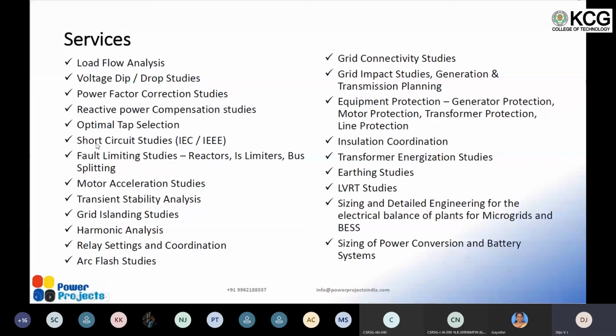Short circuit studies based on IEC and IEEE standards, fault limiting studies with reactors or current limiters or bus splitting, motor acceleration studies. We do transient stability studies, grid islanding studies, harmonic analysis, relay setting and coordination, arc flash studies, and we do grid connectivity studies, grid impact studies, generation transmission planning, equipment protection, generator protection, motor protection, coming under the protection umbrella. The insulation coordination is a very specific study with respect to over voltage and transient, temporary over voltage and all.